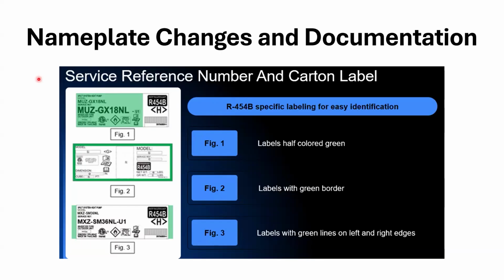Maybe you have multiple orders on that job, or they're being delivered from Gensco, and maybe the equipment gets mixed up there. Then when it gets sent out to the job site, I would maybe do some training on that process and make sure everybody handling that equipment is on the same page and understands this labeling system. So you're not getting out there on site with the equipment not starting and running, and you find out you have an R410 branch box on a 454B smart multi outdoor unit. So you see how that happens, right? Everybody involved needs to be on the same page, from the guy in the warehouse putting the job together and sending it out the door to the installer. It's going to happen. We're in a transition from one refrigerant to the next, and we have a mix of equipment out there. Right now it's really tough until we get that 410 equipment gone and out of the way, and then R454B won't be as bad. But right now, it's happening.